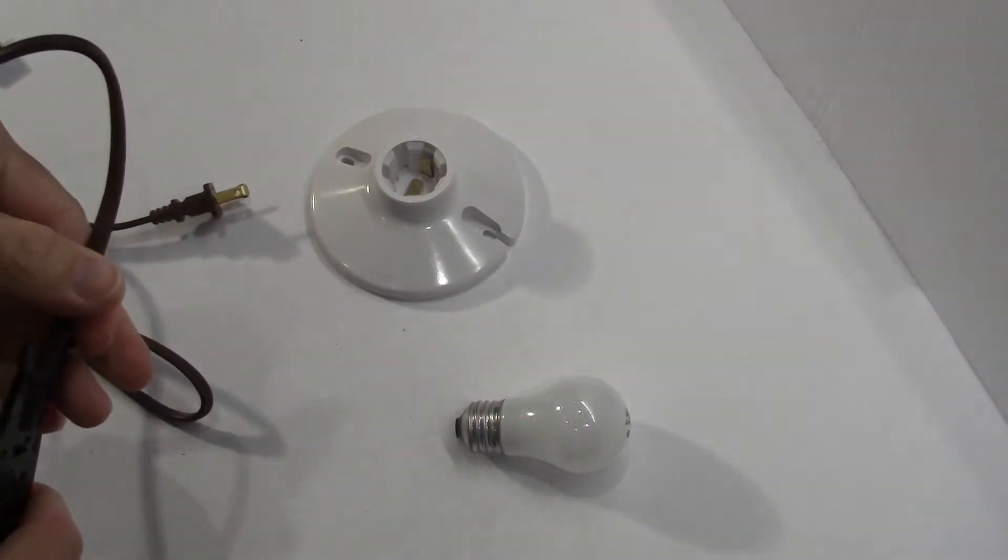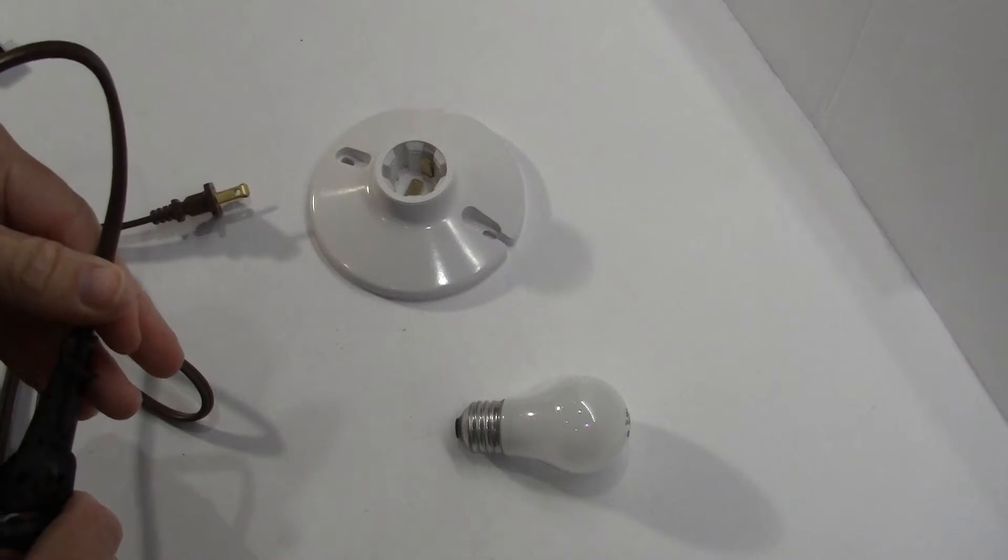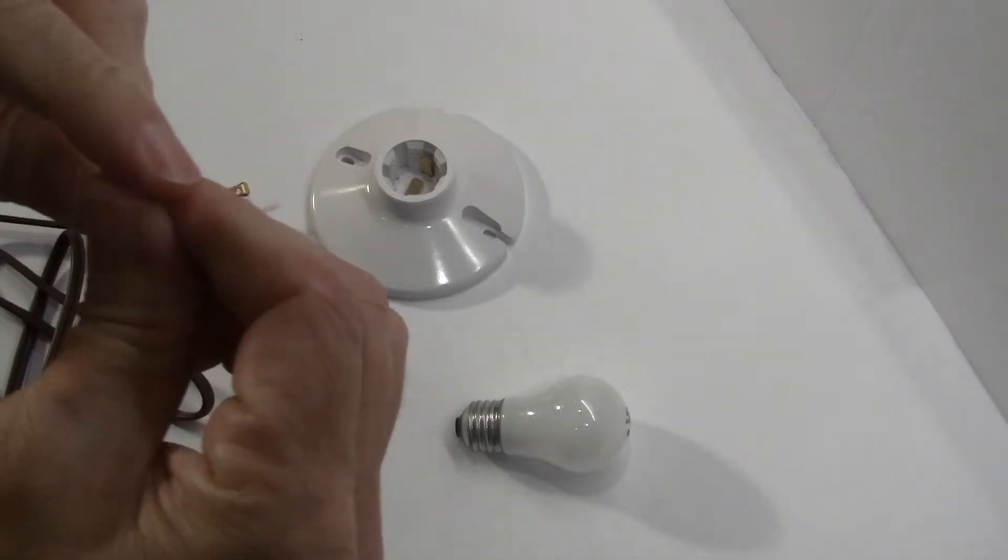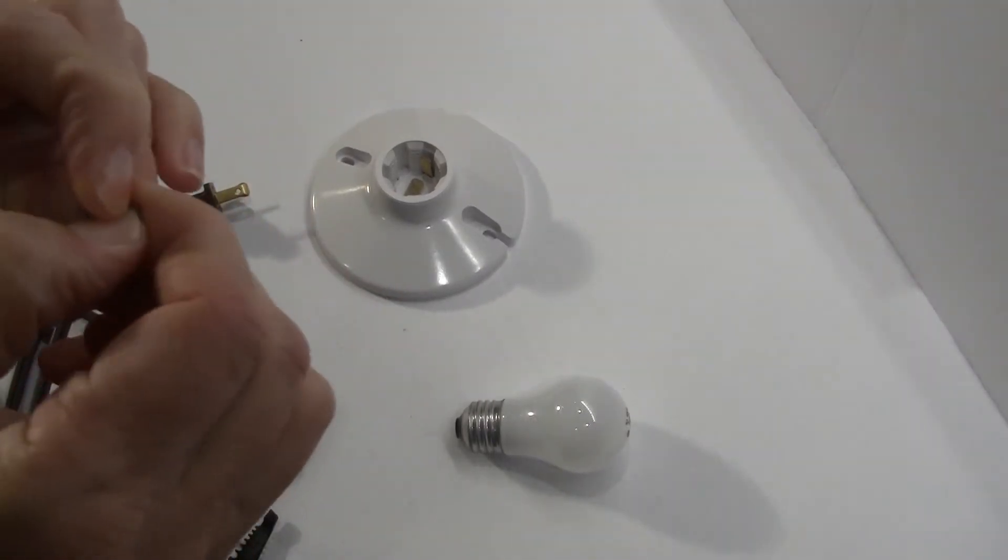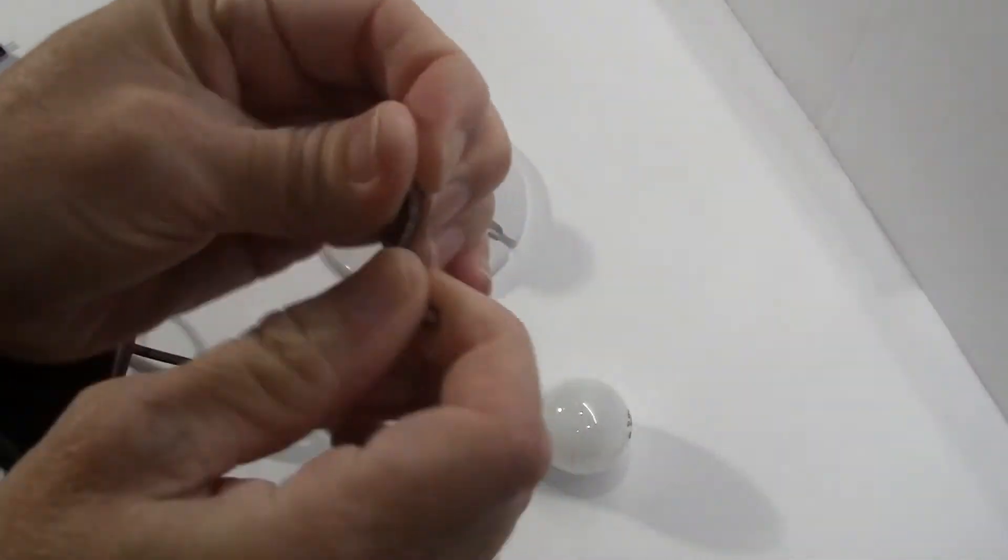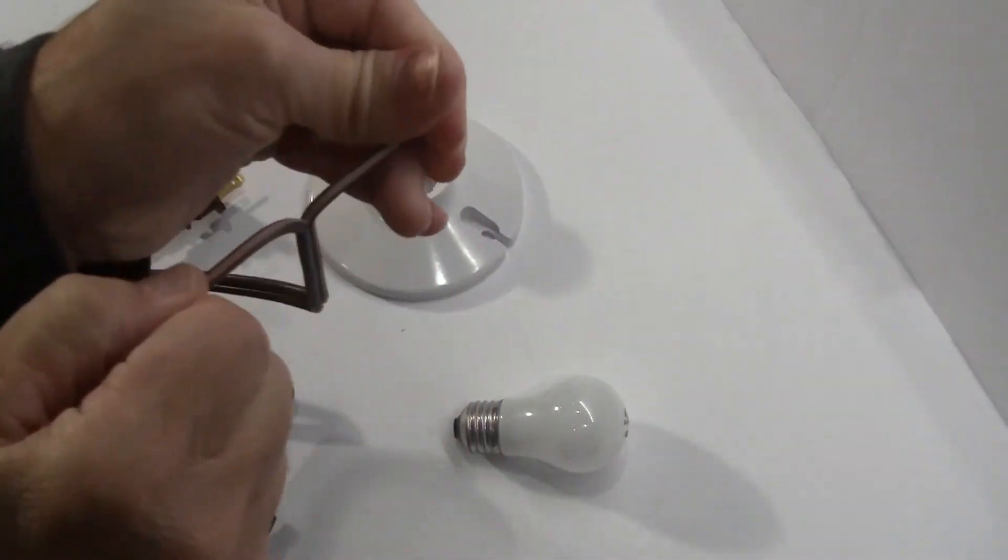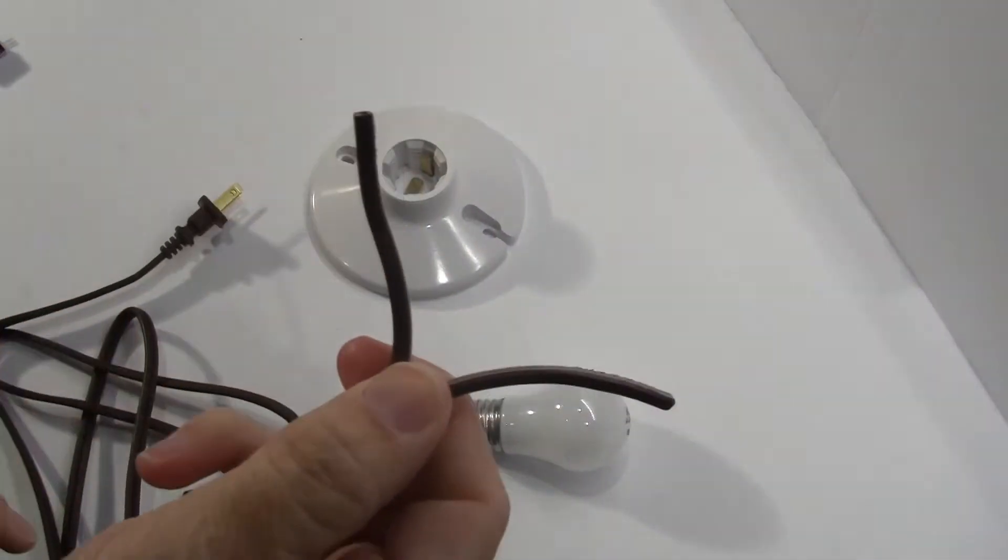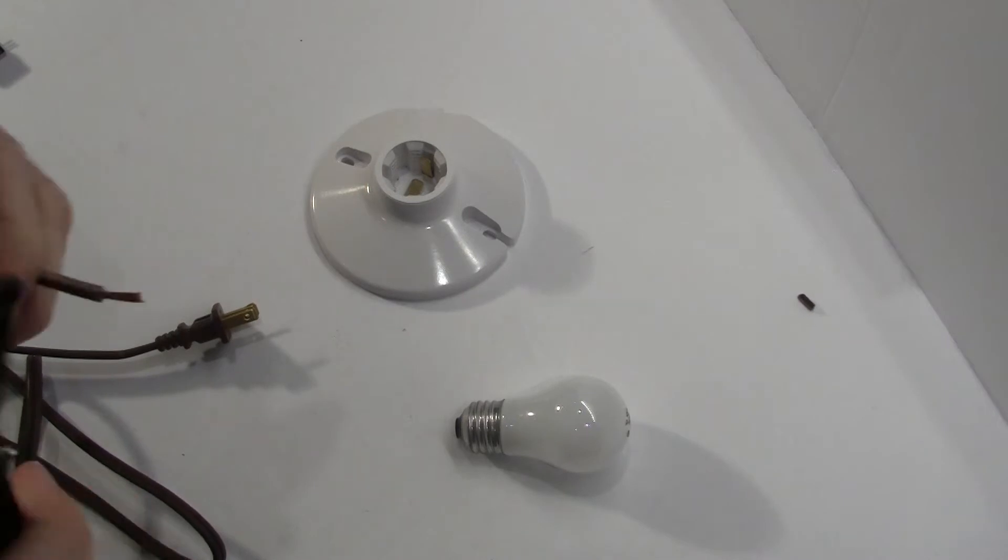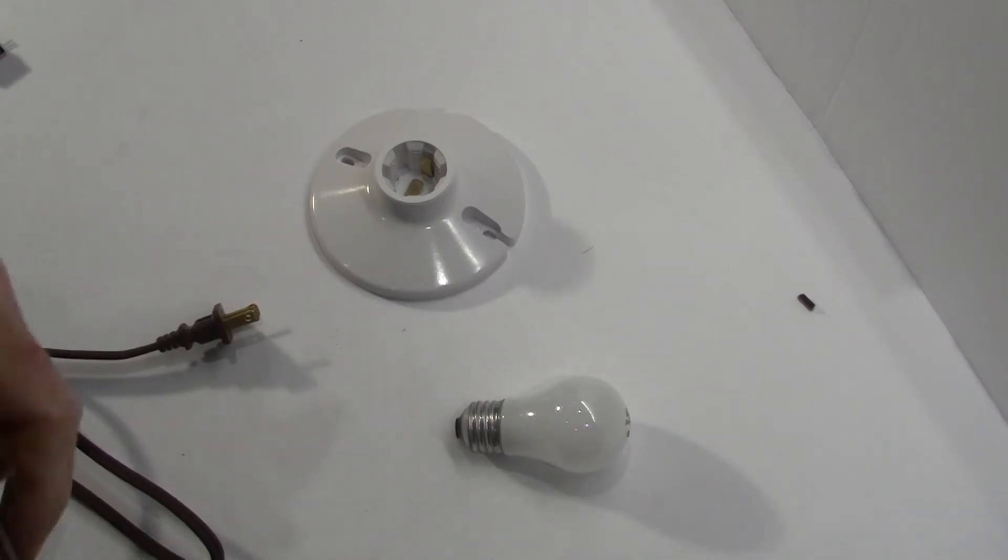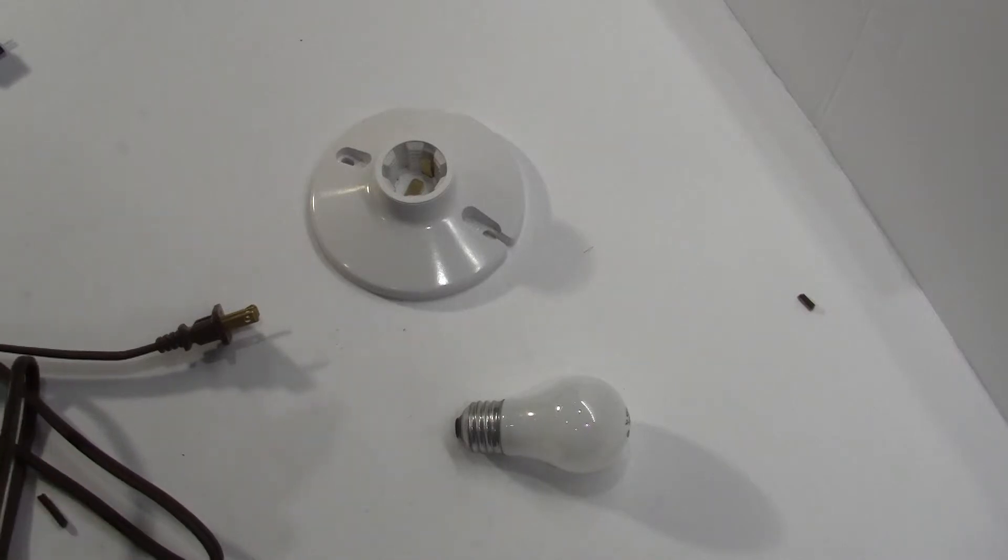Next step is to splice the two wires, so that we can connect them to the light fixture. Be careful to get this right down the middle, otherwise you could have exposed copper, which could cause a short. I'm going to strip the wires and leave about three-quarters of an inch remaining. I'm going to twist them up so that I can attach them under the screws of this light fixture.